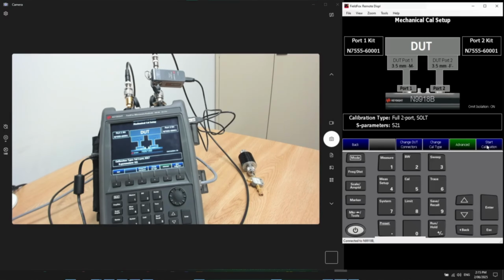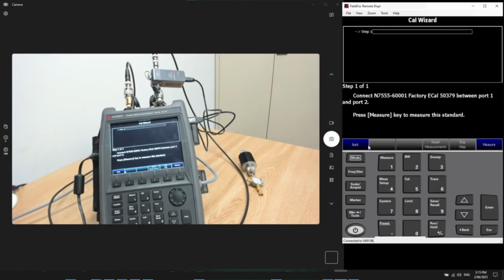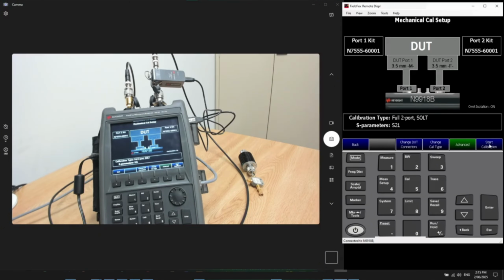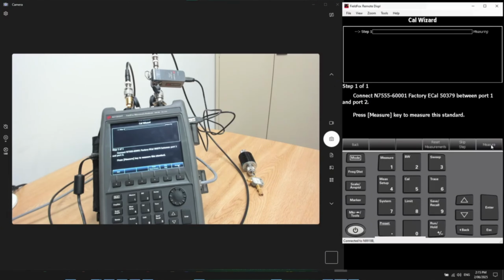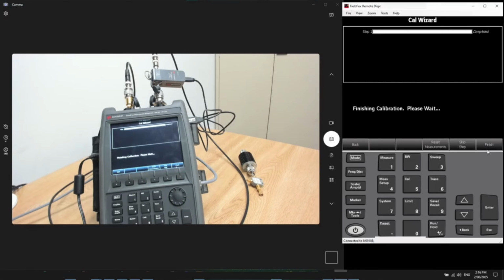Right, I still couldn't find my top range, but you should use that. So then we can start calibrations. So we connected the ECal between port 1 and port 2. And we click measure. It depends on the number of points and also the IF bandwidth that you set, and it will determine how long the calibration will take. Click finish and we are done.